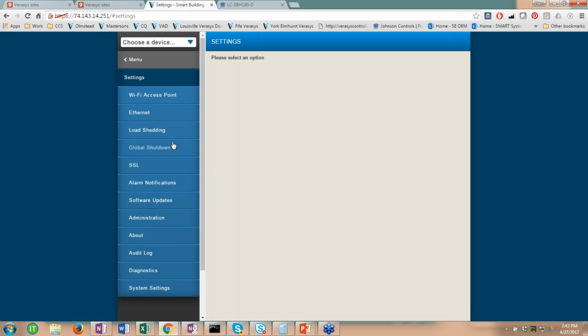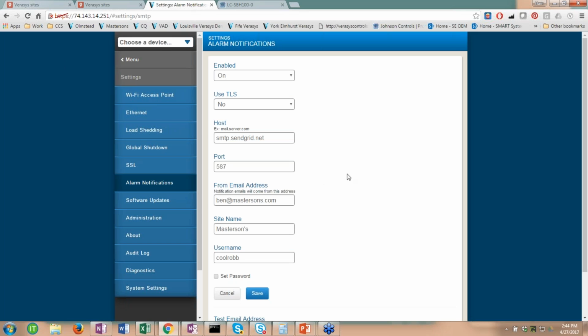We also have other features. This is where you set up your Ethernet connection into the system. This system is also capable of providing email and texting. You come into the alarm notification and set up your email address and a server email address. We have all this documented on how to do it. To set up the alarm notification, you only have about 7 different parameters to fill out, then you save it.